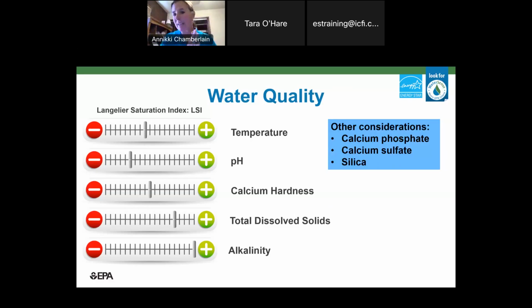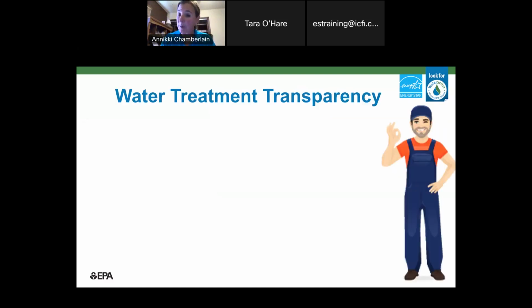So, like I said, nothing we need to get too crazy about, but it is something that we need to know is important because this person right here, who you're paying money for, is kind of the key, very cost-effective key to managing correctly. So what we need to know is that this person is taking that water quality into consideration and giving us the service that we're paying for. So typically, salespeople come in, and say, hey, if you buy my chemical program and my service, I can get you running at 4 cycles of concentration. So that's what we expect.